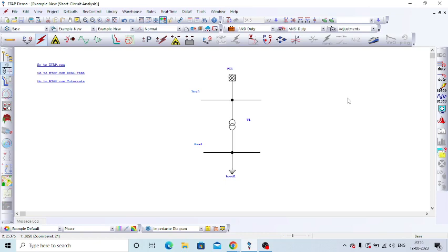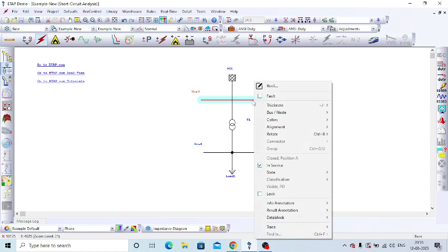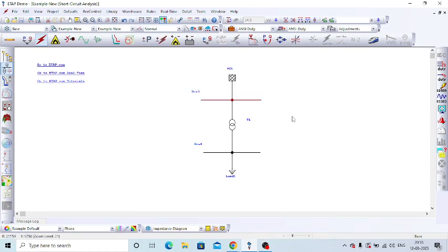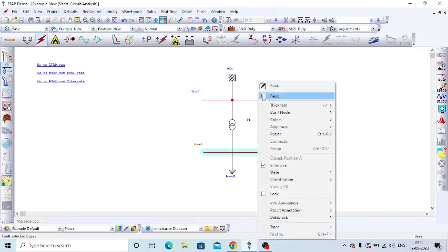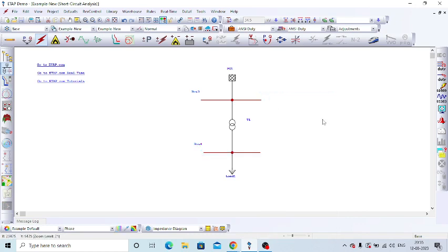Okay, so in a practical power system, an electrical fault can happen anywhere in the power system, in the transmission line or in the bus, and also in the equipment. The fault can happen internally to the equipment or outside the equipment. But in the software, mostly in this ETAP, we can have the fault mostly on the bus only. If you select the bus, right click, then make it fault. So the buses for which we want to calculate the fault current, we can select.